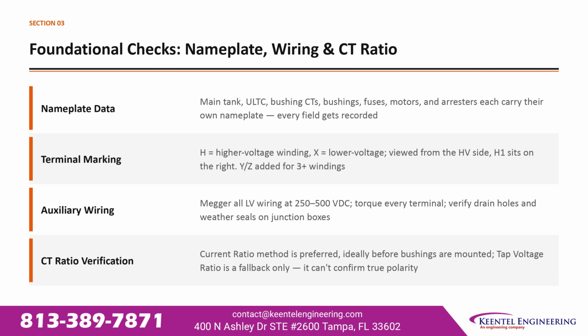Every nameplate matters. The main tank, the tap changer, bushing CTs, bushings, fuses, motors, and arresters each carry their own, and every field gets recorded. Terminal marking follows a standard. H marks the higher voltage winding, X the lower voltage. Viewed from the HV side, H1 sits on the right, with Y and Z added for units with 3 or more windings. On auxiliary wiring, Megger all low voltage wiring at 250 to 500 volts DC, torque every terminal, and verify drain holes and weather seals on junction boxes.